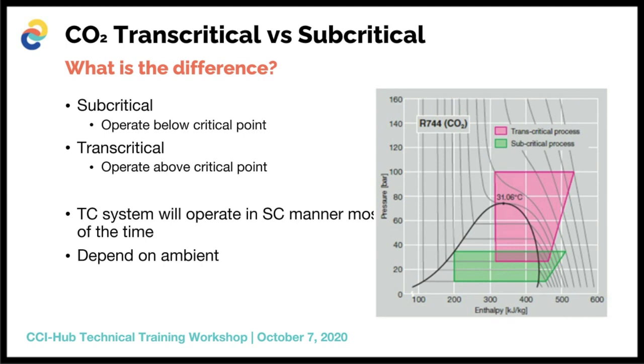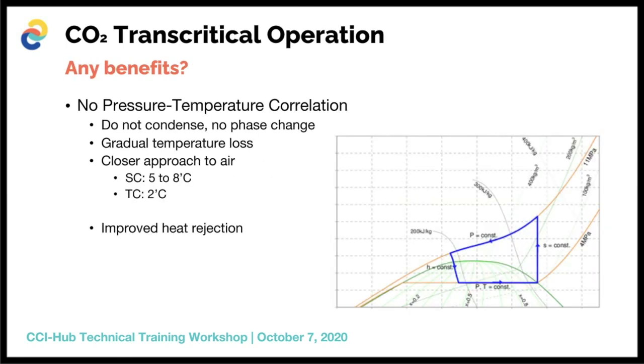So then basically also a lot of people ask me the questions around, is it only negatives or is there benefits between having a plant operate in a transcritical manner? So basically, there are benefits actually of running a plant in the transcritical manner. The first benefit of it is that basically there is no pressure-temperature correlation. What this means is that you do not condense your refrigerant on the high side, so you also do not have a phase change. So what you will find rather is a continuous drop or rejection of temperature as it goes down according to the ambient conditions or the air conditions.